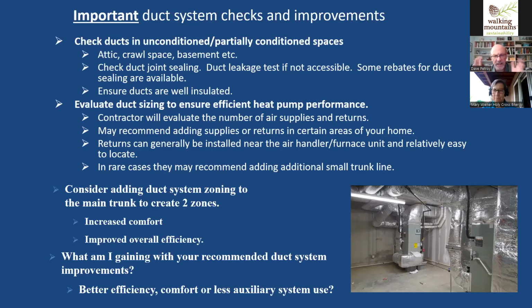They're going to look at duct sizing for heat pump performance. Heat pumps typically need bigger ducts than furnaces because the temperature's lower, but you're not going to go in and build a bunch of bigger ducts. All they're going to do is look at it and say, I can add some returns here, maybe a little air supply here, and it's not too bad to do.